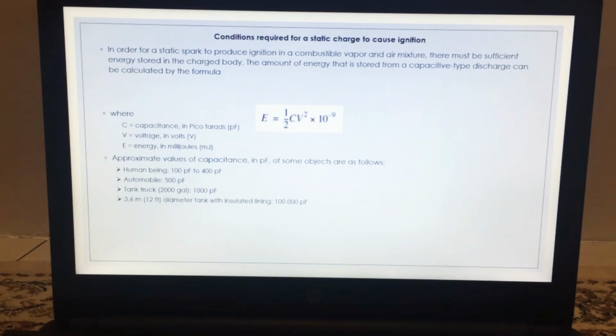Condition required for a static charge to cause ignition. In order for a static spark to produce ignition in a combustible vapor and air mixture, there must be sufficient energy stored in a charged body. The amount of energy that is stored from a capacity type discharge can be calculated by this formula. C is for the capacitance in picofarads, V is the voltage in volts, and E is for the energy in millijoules. Approximate values of capacitance in picofarads of some objects are as follows.